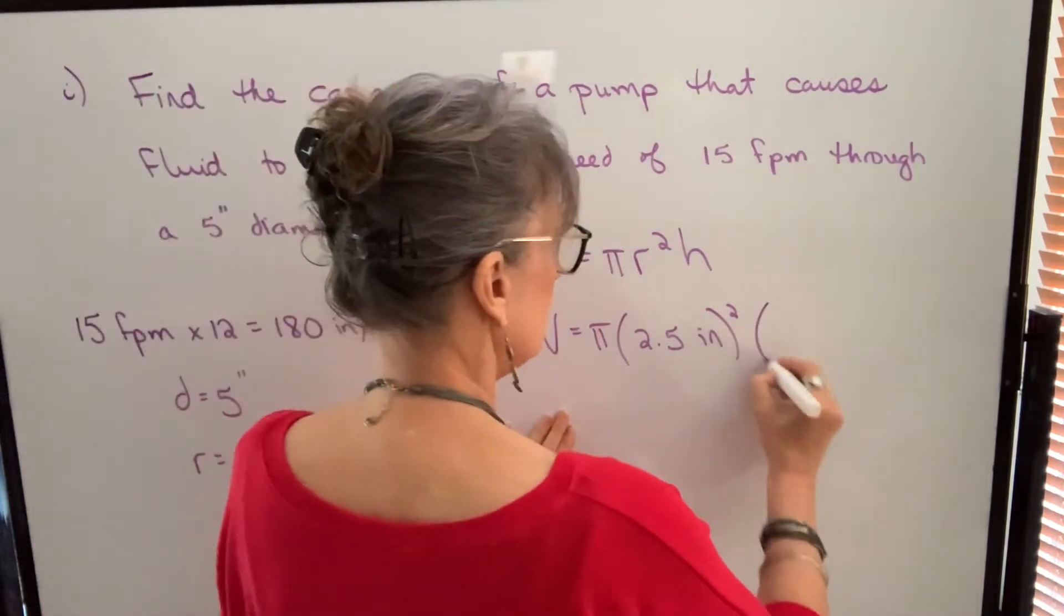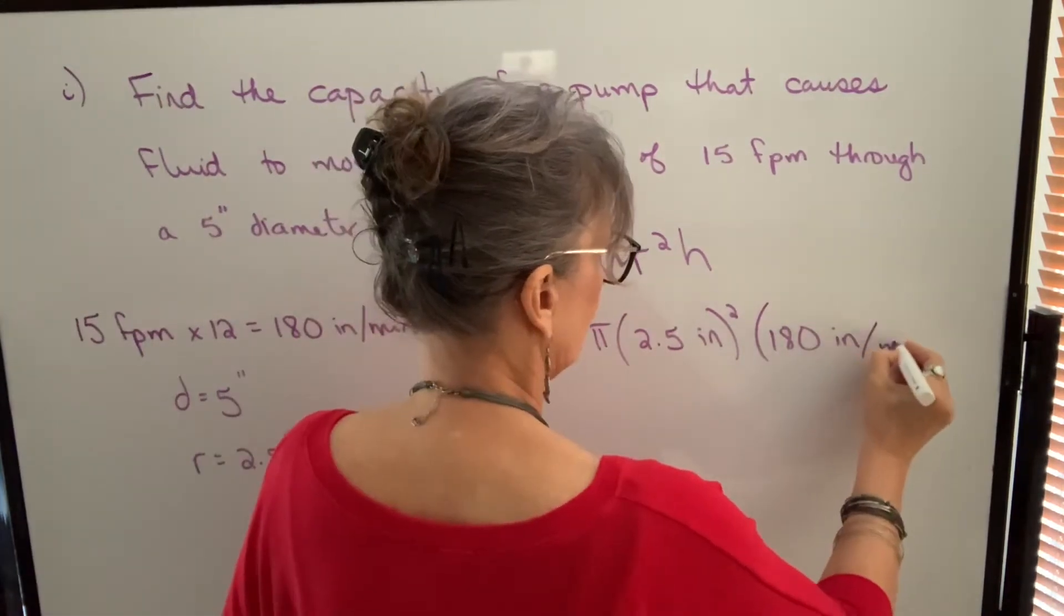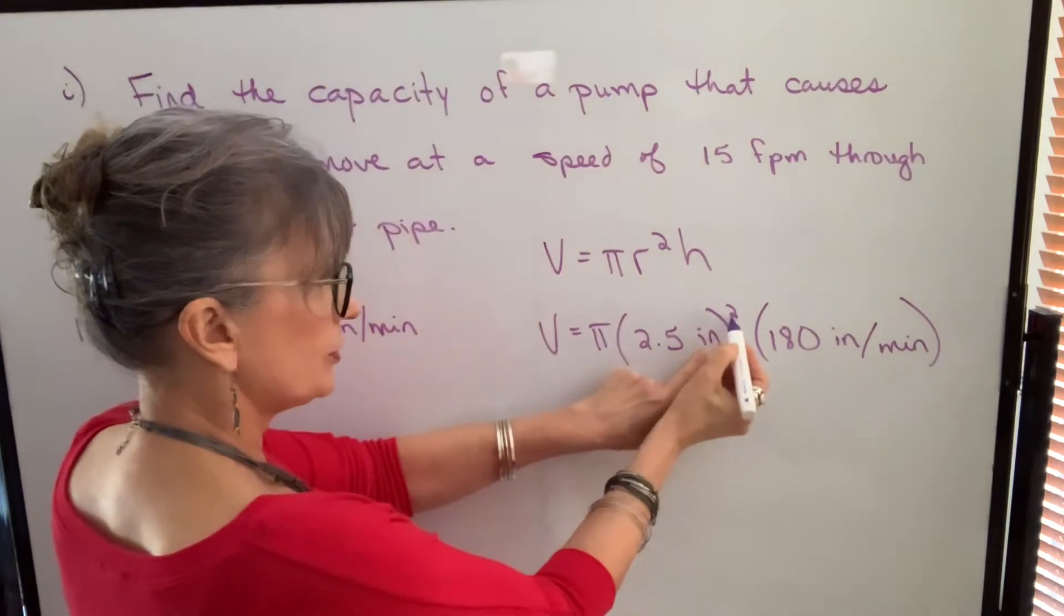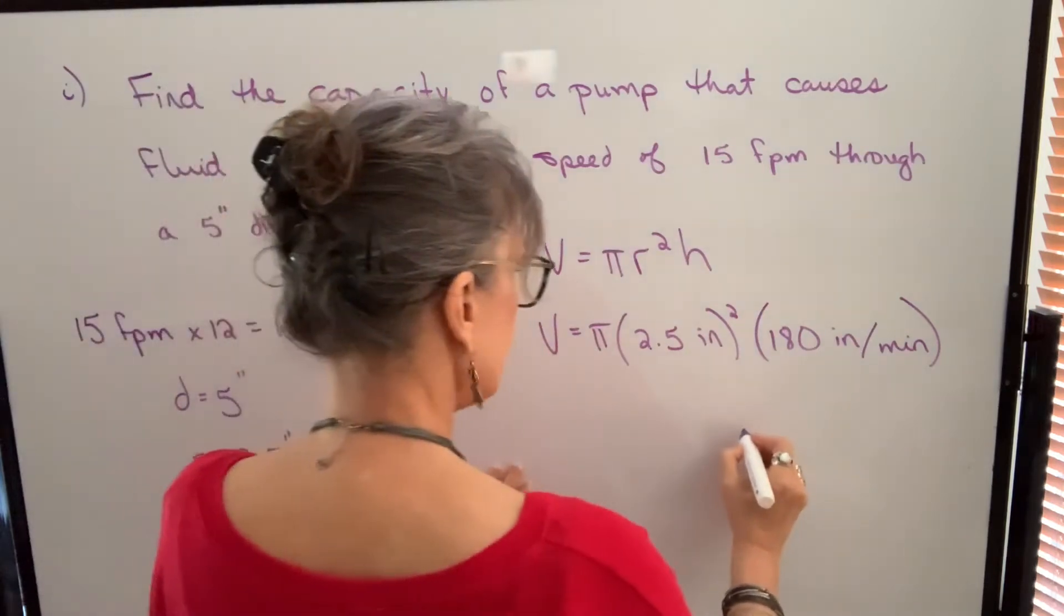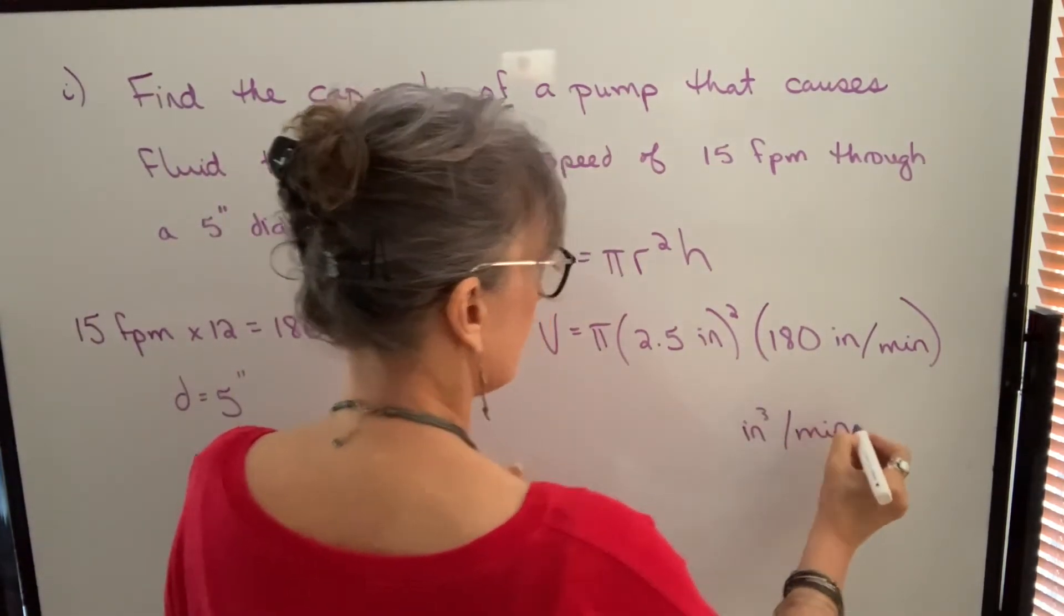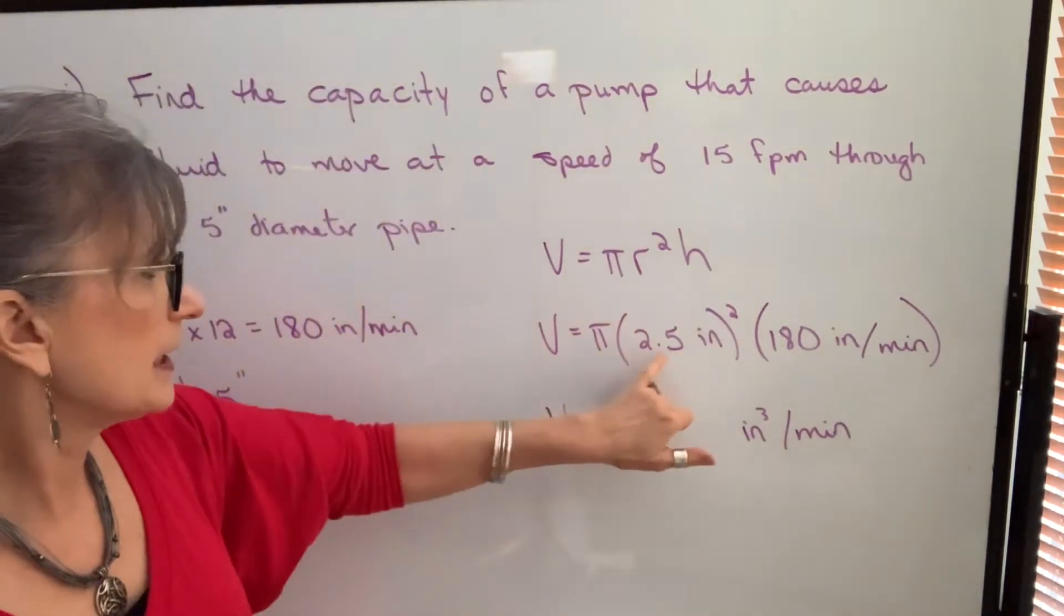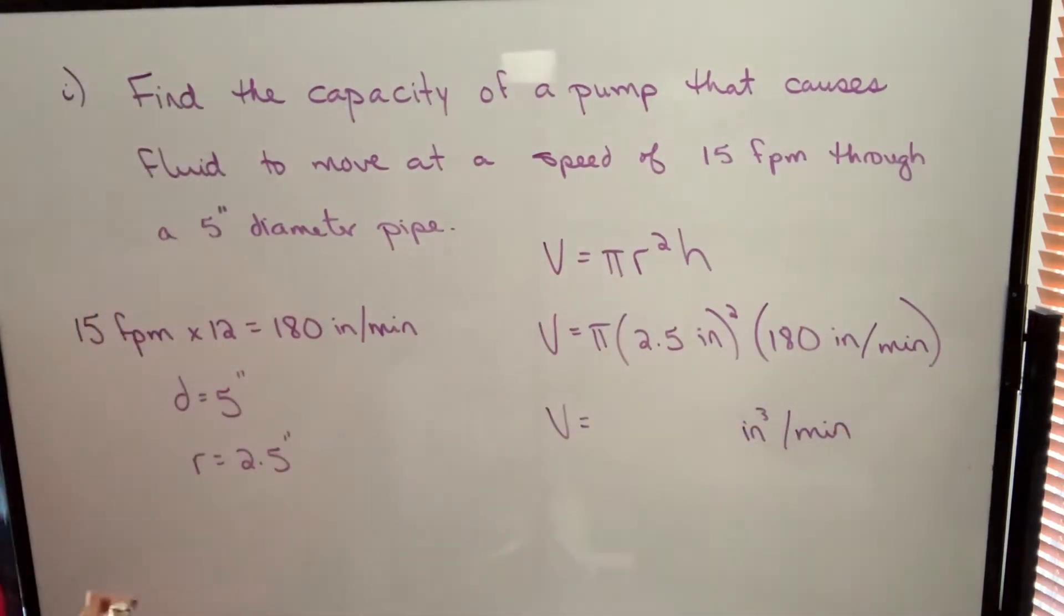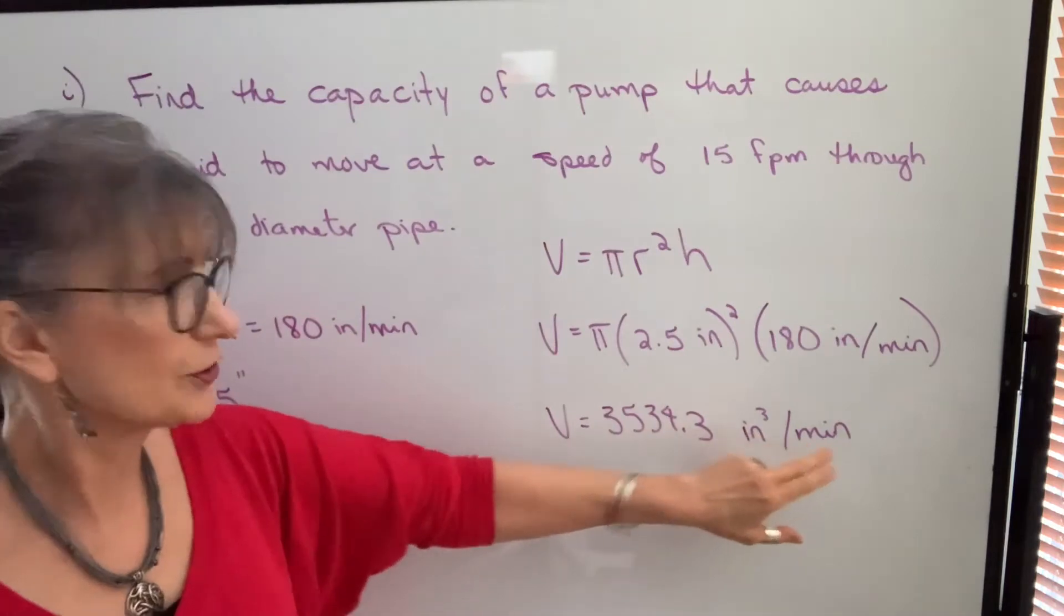So there's a total distance or height of 180 per minute. So here this gives us square inches times inches gives us cubic inches and our time factor is per minute. So we're going to end up with cubic inches per minute as an answer. So we multiply pi times 2.5 times 2.5 times 180 and we get 3534.3 cubic inches per minute.